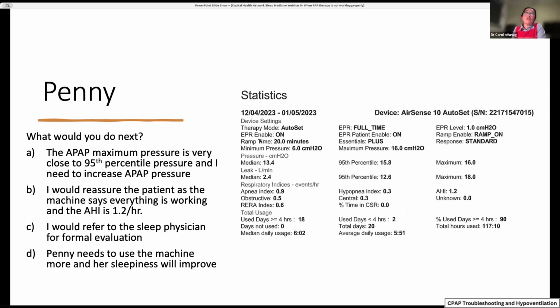These days, the CPAP machines typically have a ramp, so it can start on a low pressure, and then as the patient is falling asleep, the pressure gradually increases, and that's set on 20 minutes. Now, Penny's been using it for 20 days so far, and you can actually see that the average usage per night is 5 hours and 51 minutes. So she's definitely using it quite a bit. The machine tells us that the pressure she required is 15.8. So that's very close to the maximum pressure. But it says the residual apnea-hypopnea index is 1.2.